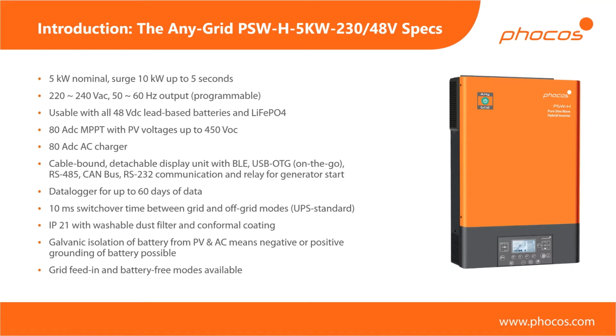We have USB OTG as a method for you to upload battery parameters or to download the data logger, for example, because there's an integrated data logger. We have RS-485 communication, CAN bus, and RS-232, primarily for communication with lithium batteries, for example. And then we have a relay to start a generator. When you have low battery voltage, for example, you can automatically start your generator. Then we have that integrated data logger for up to 60 days of data.